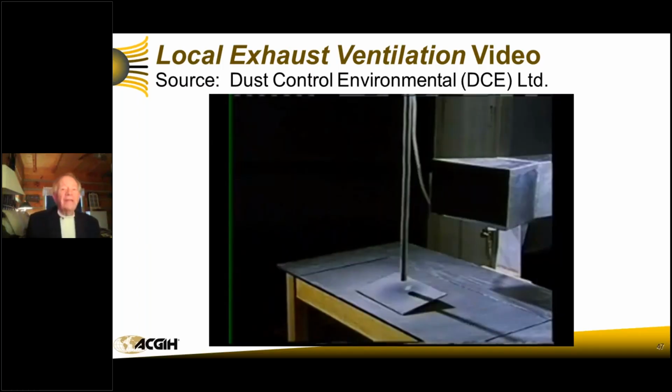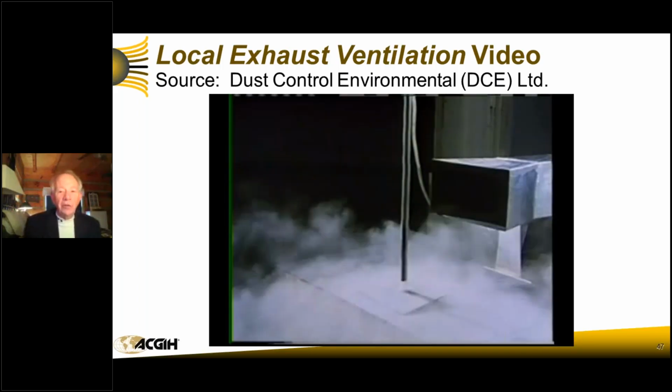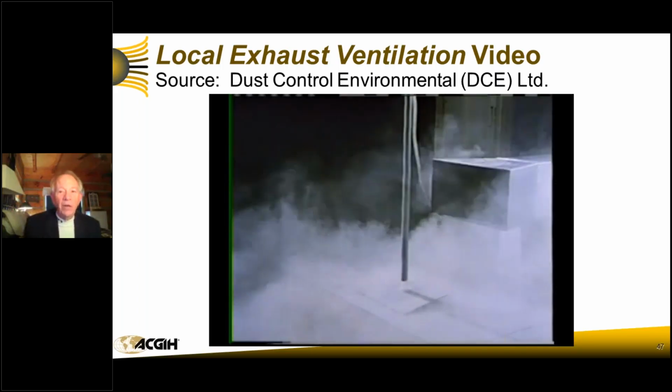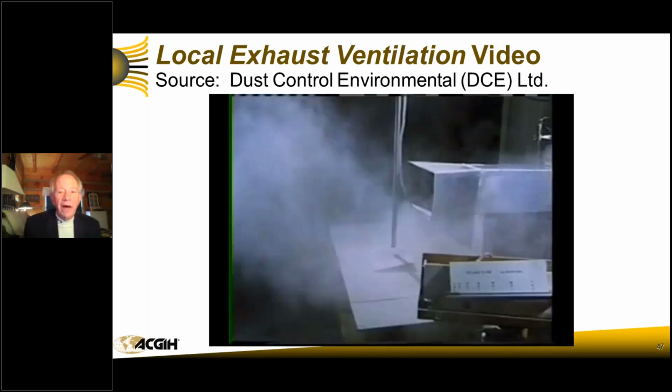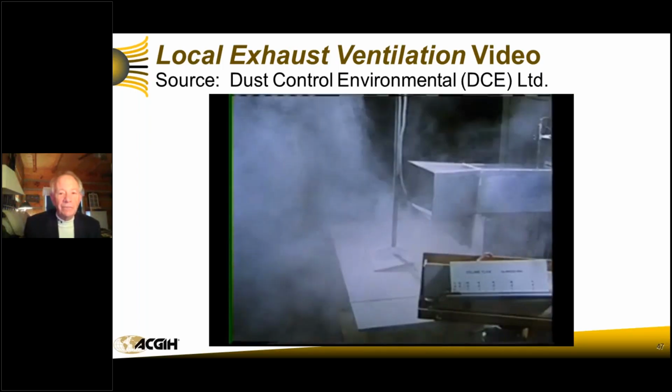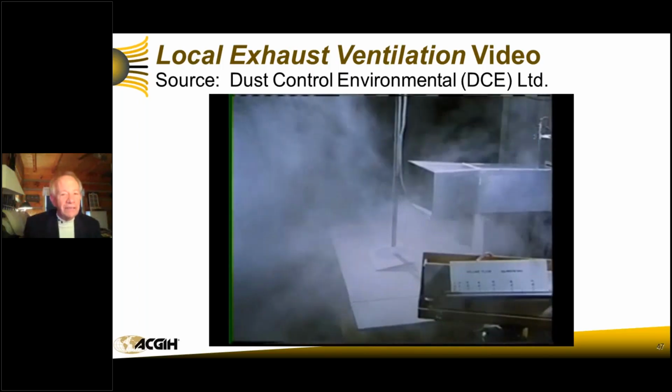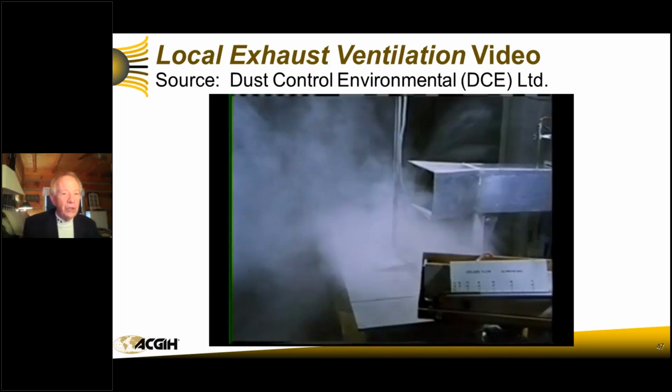Now, what I want you to see here, look at all the dust that goes behind the hood. Watch what happens to the dust that's close behind the hood. It's as effectively captured as the dust out in front of the hood.